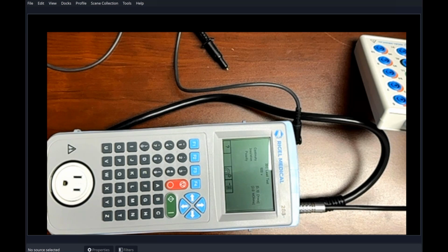So IEC 62353 is applicable in parts of Europe and Asia. The NFPA 99 code is law within the US. So statewide, it is the code that must be followed for electrical safety within a healthcare facility. Now within 62353, it's still a recurrent test and repair standard. So it's looking at electrical safety for devices that are in circulation. So it's very similar to NFPA 99. They're both performing tests that are for preventative maintenance, acceptance test, post-repair.